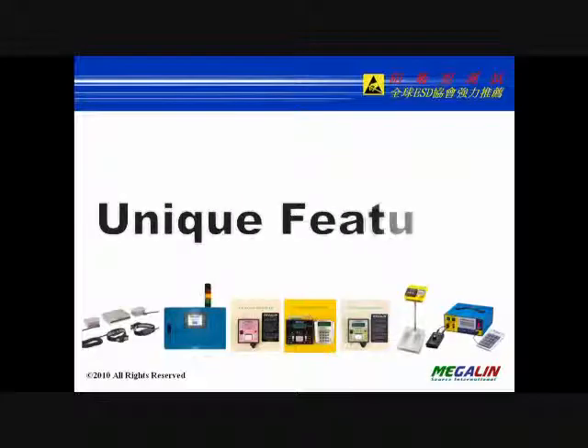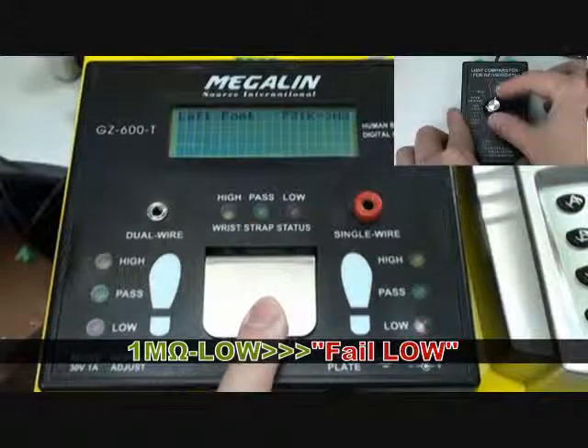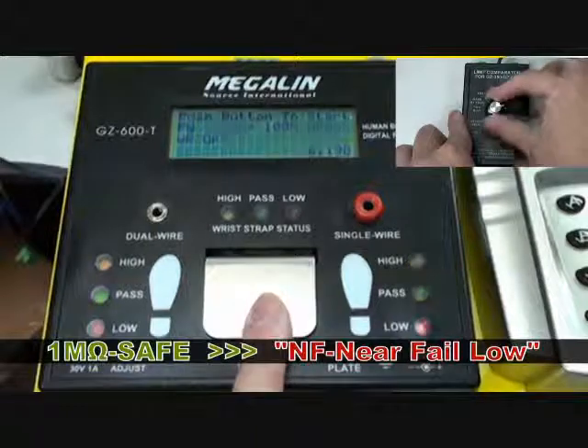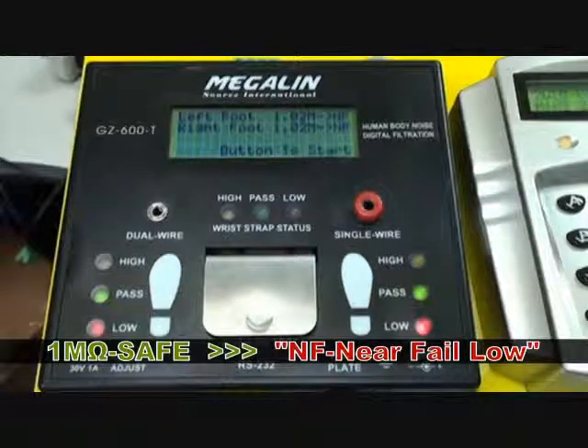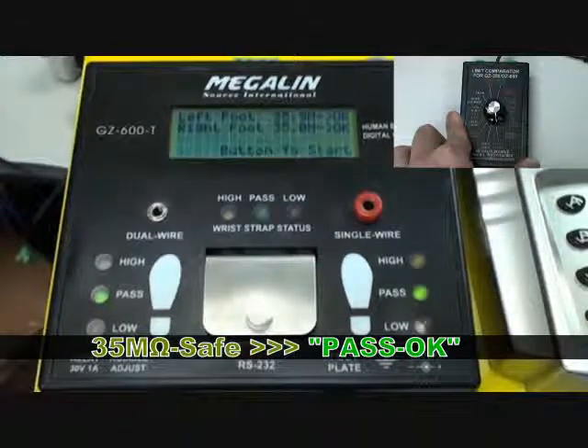Next, we are going to simulate the footwear testing with a dedicated calibrator. Select the 1 mega low range — the result should be fail low. Select the 1 mega safe range — the result should be near fail low. Select the 35 mega safe range — the result should be OK.